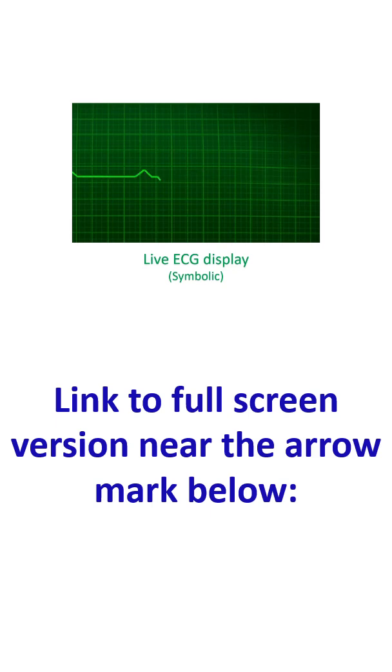Some Holter recorders have a live display of the ECG which will help to verify proper attachment of the patches. In such cases, electrode patches can be repositioned if needed to get better waveform display. Make sure that the patches are attached well and do not produce artifacts in the display.